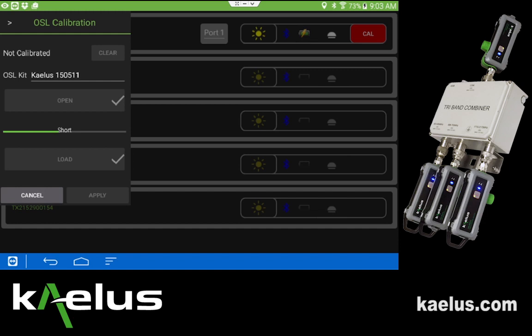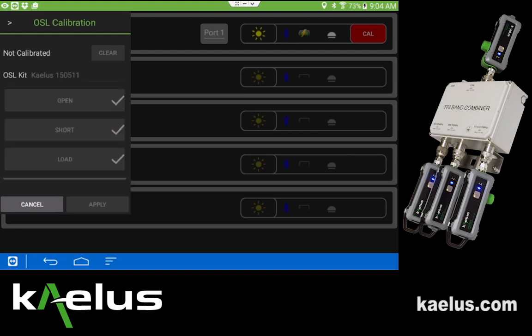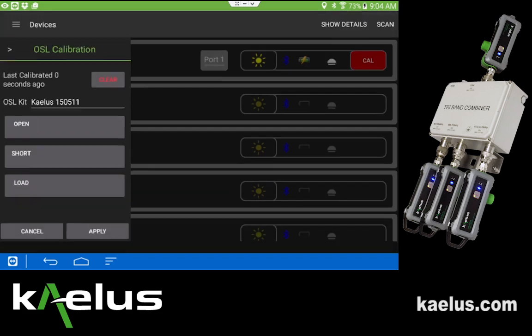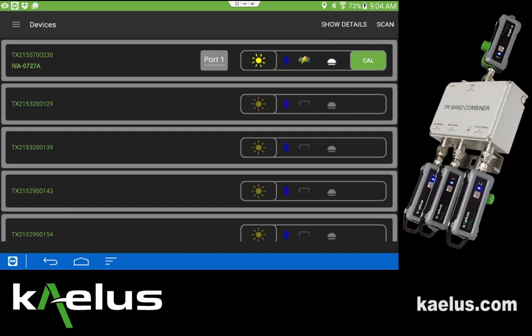Once all three standards are complete, we'll be offered the opportunity to apply the corrections that are calculated based on these OSL standards. By pressing apply, correction factors for the OSL kit are applied, and we return to the devices screen where we now see that cal is good.